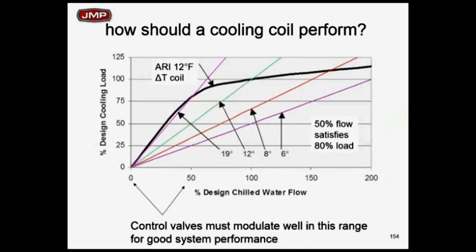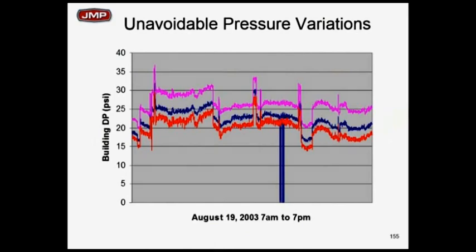What delta T? The delta T is colored. The 12-degree delta T is that bluish, green line. The purple or pink line at the top is what the delta T would be at 50%. So at 50% flow, the pink line crosses the black line right about 50%. That pink line is 19-degree delta T. ARI is telling you that as you reduce flow in a cooling coil, your delta T should go up. Why in the real world is that not happening? Why are we not getting a higher delta T across two-way valves and cooling coils at part flow?